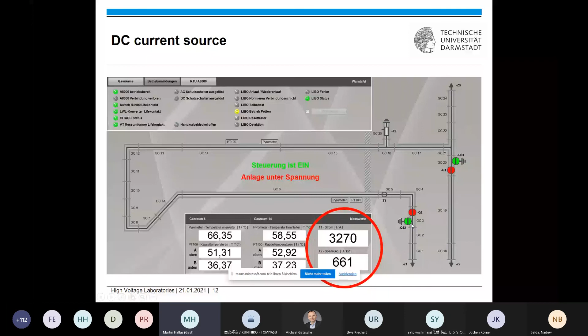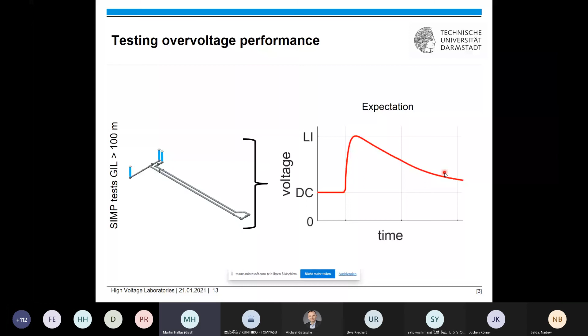So the next topic in our project is the testing of the overvoltage performance. Remember, we have the test loop of approximately 100 meters. So you now would say, okay, 100 meters, let's put a lightning impulse voltage on it. We want to make a superimposed test, which means DC and then a lightning impulse on that. And you would expect such a shape. And when you would do this, you would not get this, you would get this here.